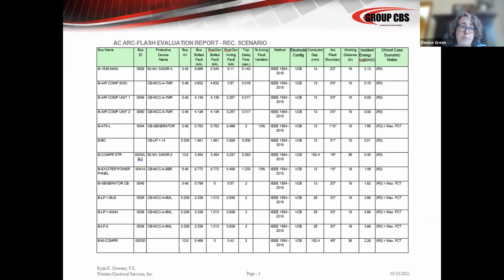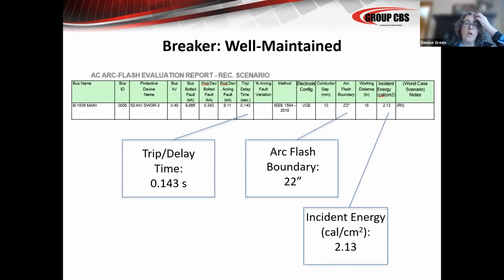So when we talk about trip times and incident energy as related to breaker maintenance, this is an arc flash evaluation report, a standard report that was done by our engineering service group. I'm going to zoom in on the main breaker. This is the main breaker from that system, and these are all the settings for the trip unit and what method was used. You can see that this was calculated using the 2018 formulas for IEEE 1584. You can see that this breaker has a trip time delay of 0.143 seconds.